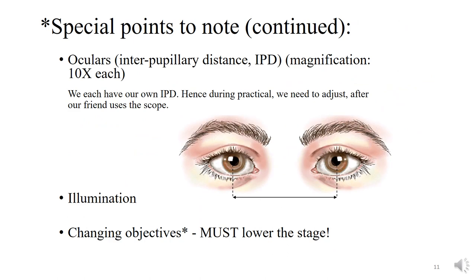Another special point: we each have our own interpupillary distance — the distance between our two pupils. For some of us it may be wider or narrower, so it is important to adjust the ocular legs to get a good view of the image.